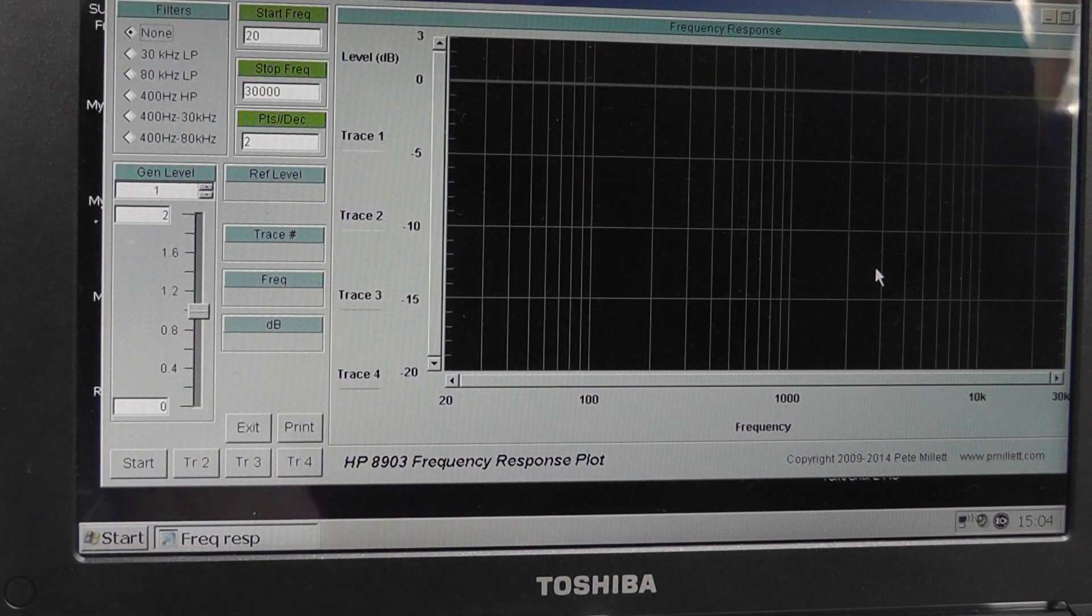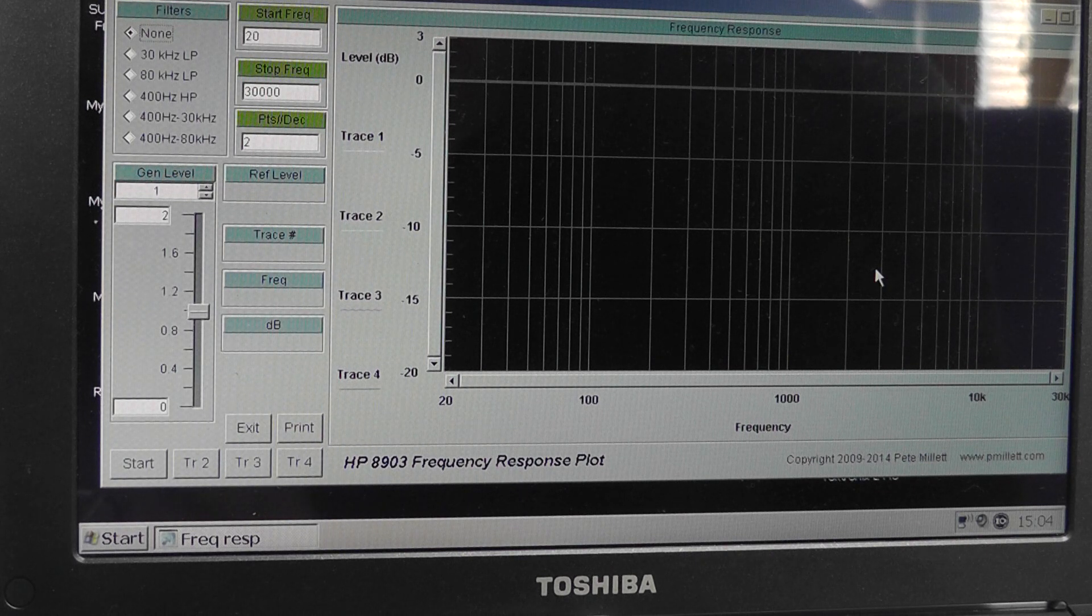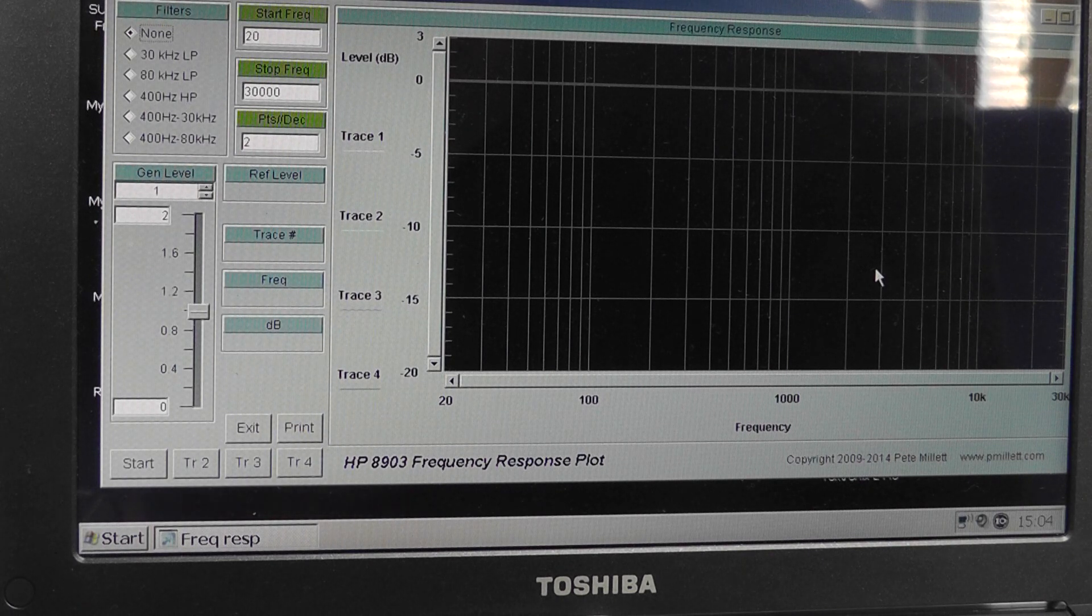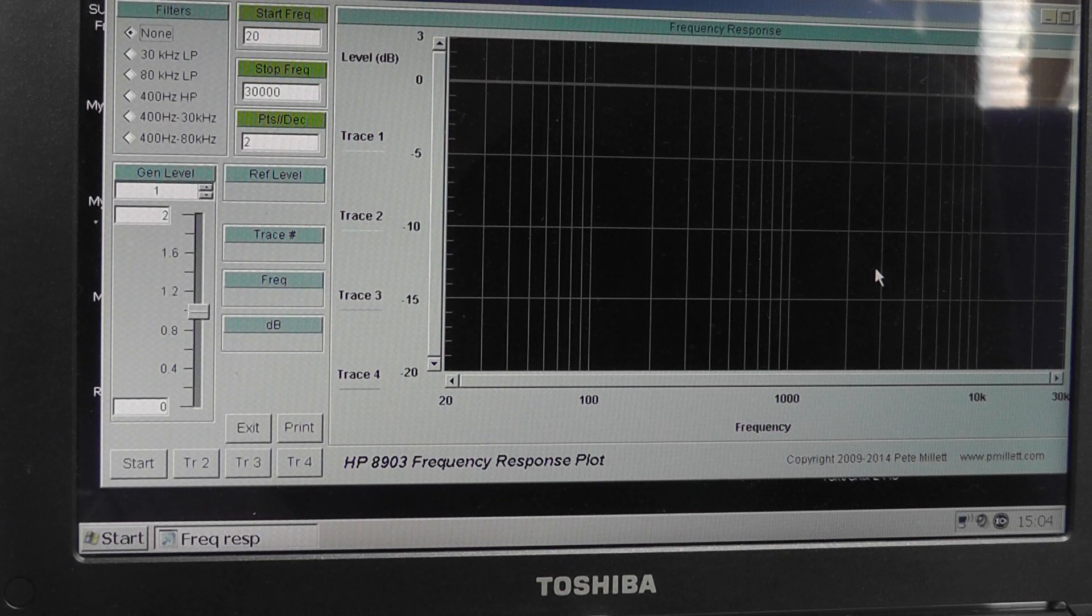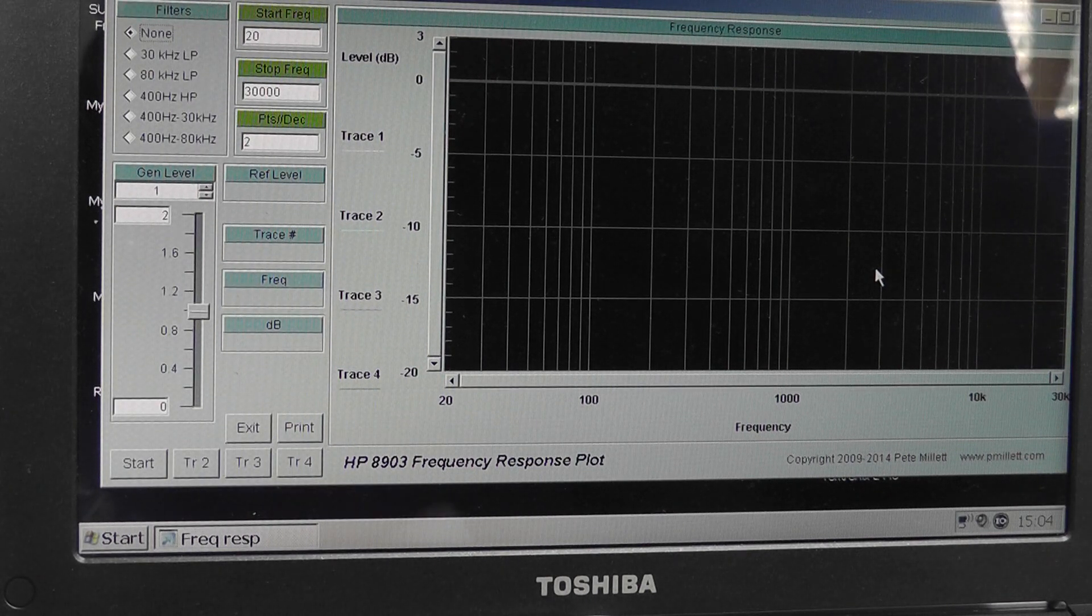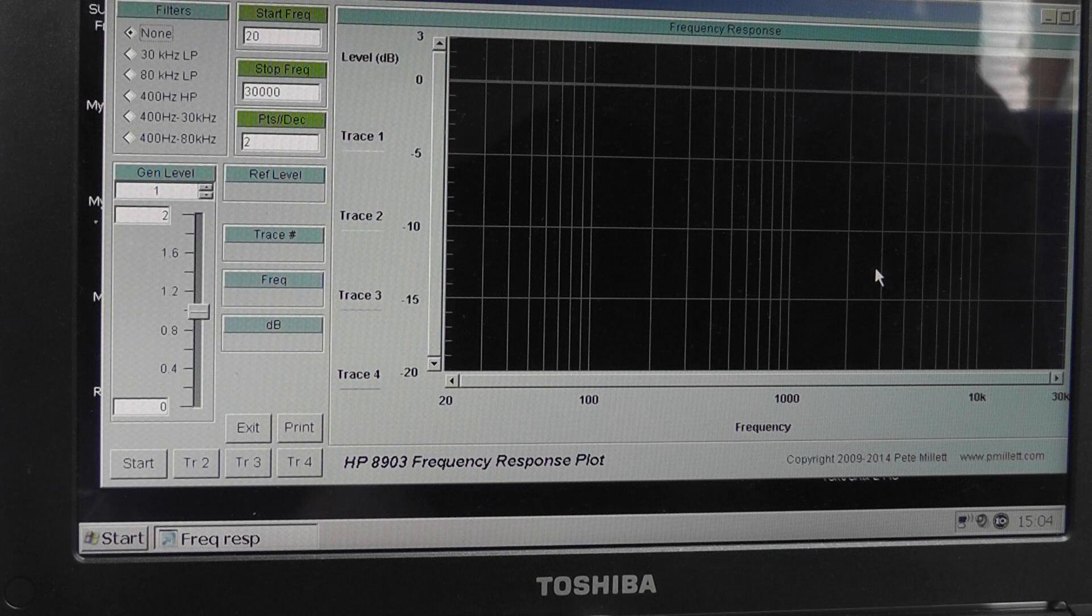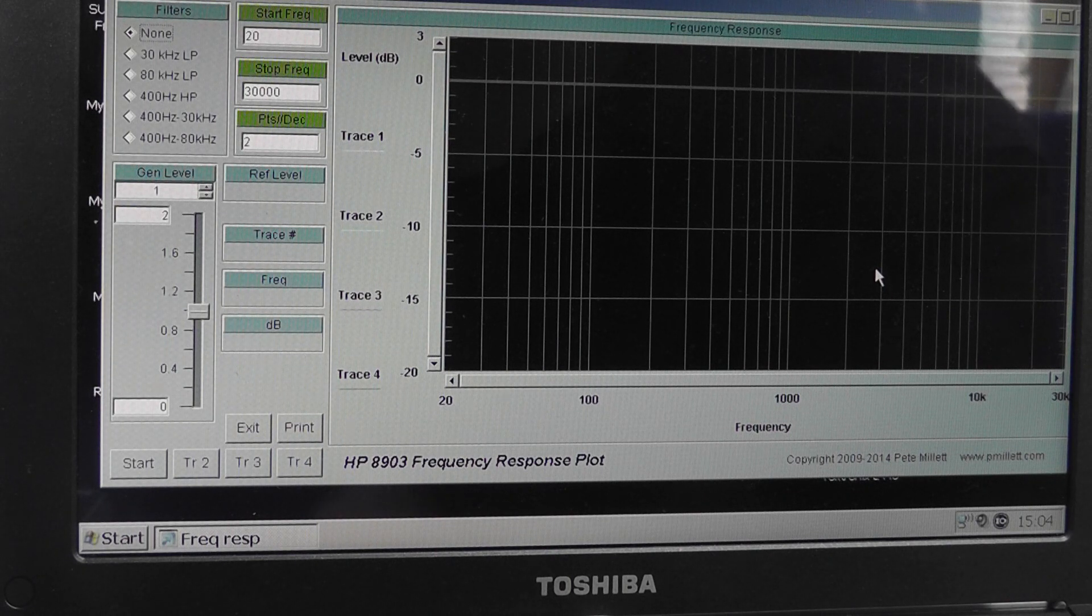So what the problem I was having—and it's working at the moment—now when I open this up, I'd have a message saying 'cannot find an audio analyzer, please add it from the instrument list.' Now as I say, it seems pretty critical that you spell it right. If you spell it wrong, it's looking for that name. It's not looking for any sort of port address or anything—it's looking for a name. If it doesn't see the name, it thinks the item's not there. It seems to be that because this is such an old piece of software—hardware, this analyzer—it doesn't actually support plug and play. I would expect it to look for an address or a sort of like a reference to the device rather than just a name, but it actually is looking for the name.